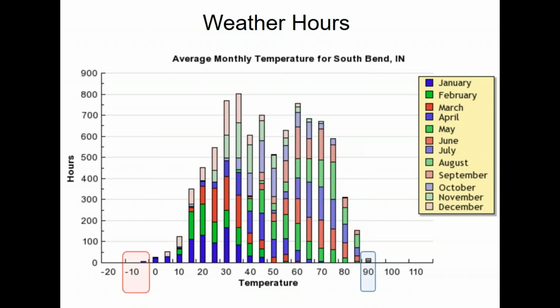Oh, I should have put this slide earlier. This is the bell curve I was talking about. So once again, I picked South Bend as my example just to pick something. I apologize if you're in a different area. But looking down at the low end of the equation, how often is it really below 5 degrees in South Bend? Not very often. It's pretty minimal. And if you look down below 0 degrees, it's like a little tiny line over there. It's really small. Same thing on the high end. How often is it above 88 degrees? Very, very small portion of hours of the year.